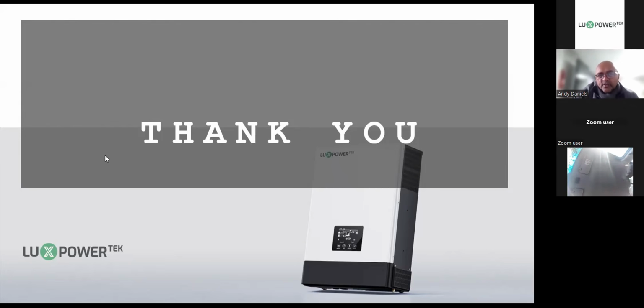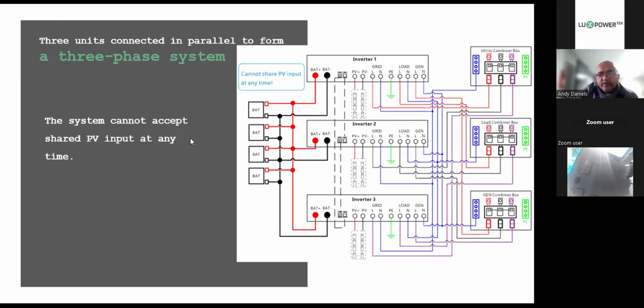So my recommendation to you is have a look at your battery and see if you have a discharge current limit. If the discharge current limit is, let's work on 48, 4,000 divided by 48, so 83 amps on 48 volts, or 80 amps on 50 volts, or 76 amps on 52 volts, then you're going to get an EPS overload, because the battery will simply not hold. So check the limit of your battery and BMS also, of course.